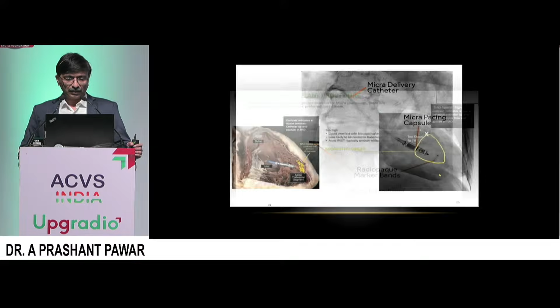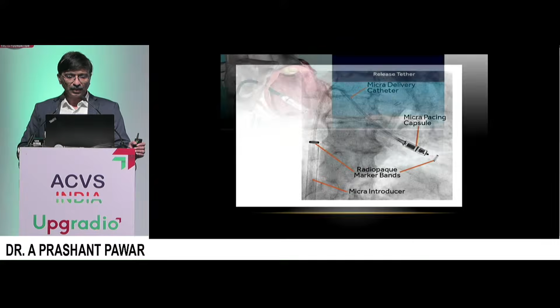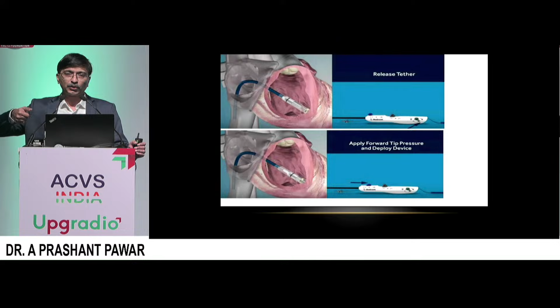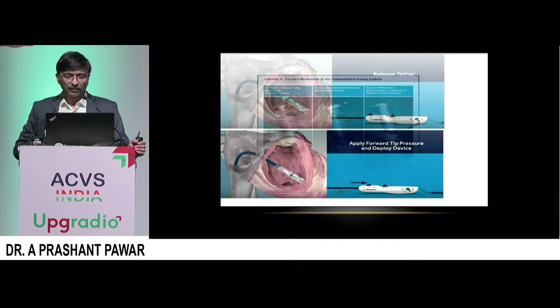So how it looks like a goose neck, it looks like a goose neck. So sheath is down, then you have this Micra delivery catheter and the Micra pacing capsule is there in this delivery sheath. Once we have achieved the location, you have to remove that lock, you have to release the tether. And then what I said, that blue is this delivery. So once we push and pull it back, it will act like a bullet, it will deliver the Micra device.